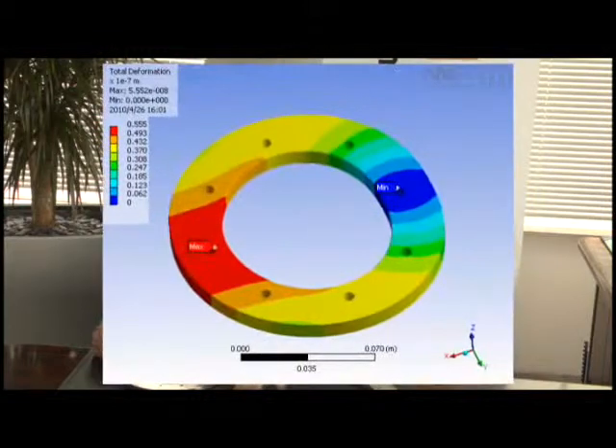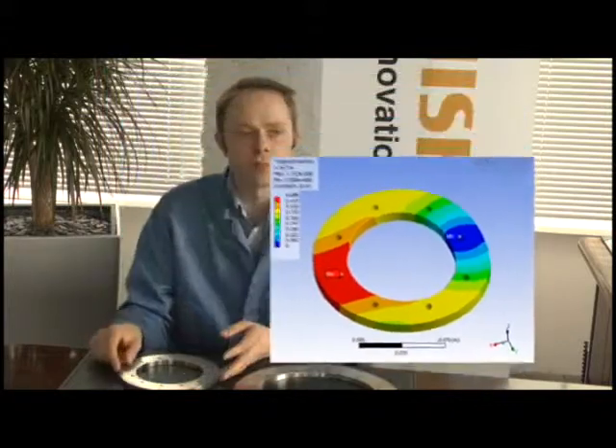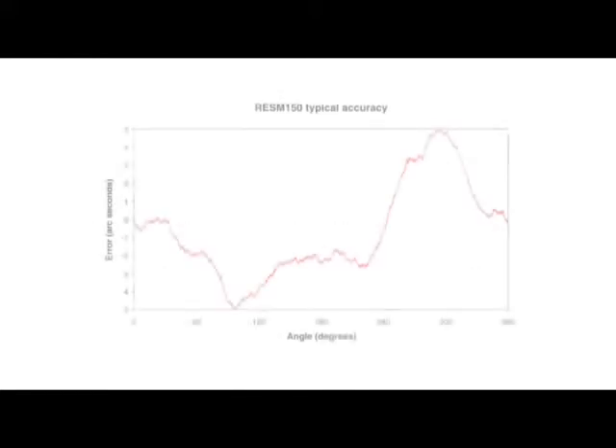Great care has been taken to ensure that the ring profile can withstand the forces involved in centering the ring, provided that the bolts themselves are clear of the ring face when the ring is being centred. RESM rings are easier to centre using the taper system. If each bolt is adjusted to the nearest 3 microns, the ring itself will be centred to on average 1.5 microns.